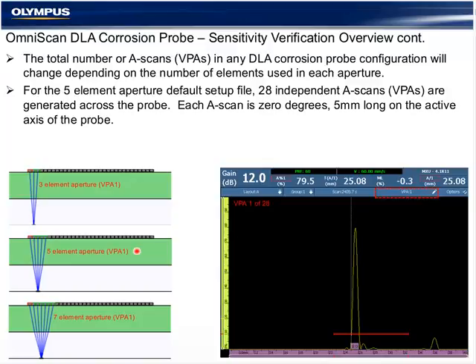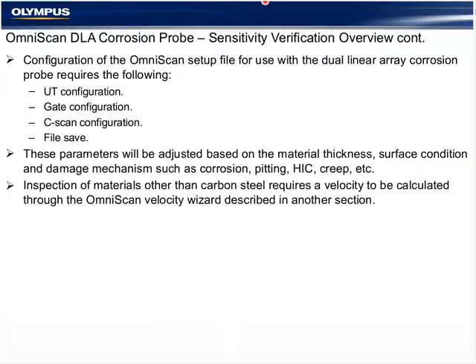results in 28 independent A scans. And we can see that depending on which of the 3 you selected, it'll be a slight difference in coverage if you're measuring beam center point to beam center point within the probe. Upon loading the correct configuration file, the setup and use of the DLA corrosion probe is divided into several sections that have been condensed for this webinar.